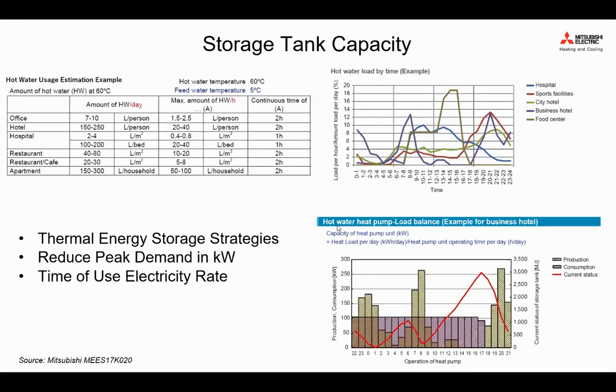Or you can purposely shift your load between hot water generation and perhaps your air conditioner, so they are not running at the same time. So let's say at 12 o'clock, you anticipate creating enough hot water for washing the dishes or preparing food, and then from 11 o'clock to 3 p.m. is where you require the most AC. Then maybe you can shift the load to reduce your peak demand in kilowatts, or you can take advantage of time-of-use electricity by storing, or by utilizing a thermal energy storage strategy.